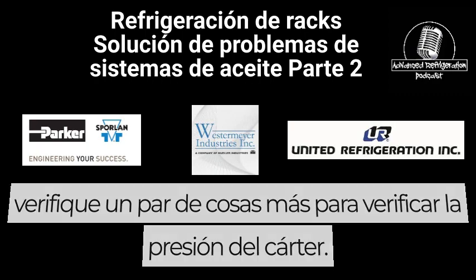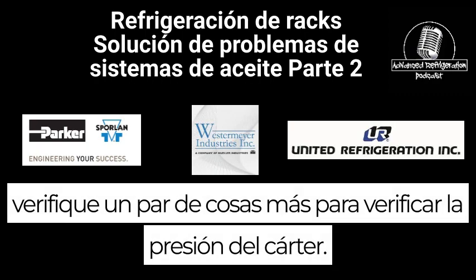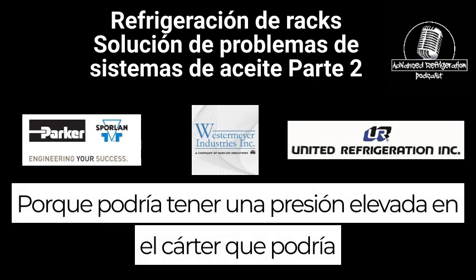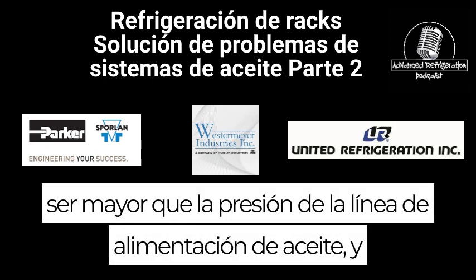you need to check a couple more things. Check your crankcase pressure. Not your suction pressure, your crankcase pressure, because you could have an elevated crankcase pressure that could be greater than that oil feed line pressure.